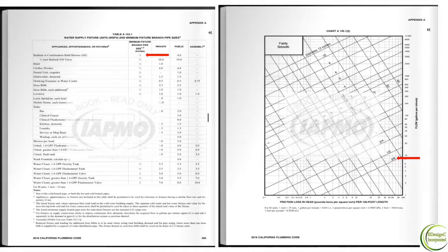And so in using Appendix A, it tells a very thorough story about what's happening and the relationship between velocity, pressure loss, and diameter. And so with that, we were able to do some pressure calcs and really flesh this out and think this through. And so for a lot of the fixtures, lavatories, and kitchen sinks, we were able to go with 3/8 inch piping. That's fairly conservative.